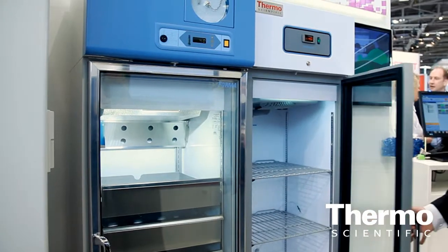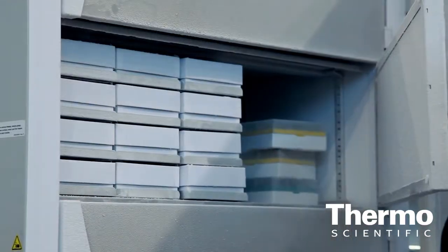Our complementary products at the show — our cold storage chain goes from controlled rate freezers, taking samples down from ambient temperature systematically to minus 40°C, where the latent heat of the sample is removed. At that point nothing will change, and then it gets transferred to the ultra-low temperature freezer. The biological clock of the sample is still ticking at minus 85°C. It only stops when it goes to the glass transition point at minus 130°C, so at minus 85°C we're not fully stopping biological activity — the biological clock is still ticking.